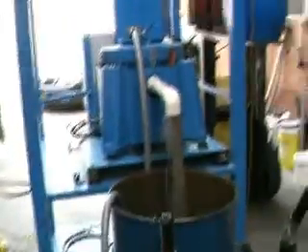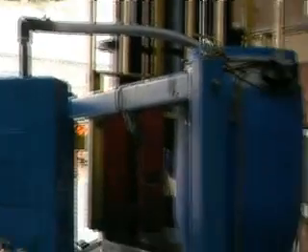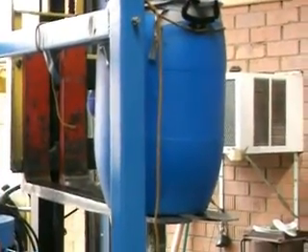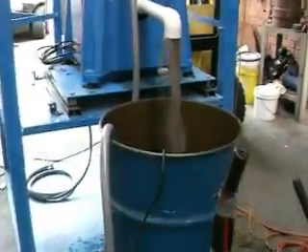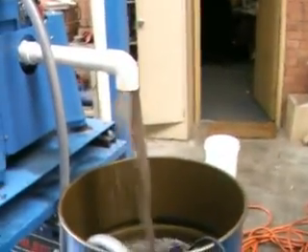Pulling about 2.8 amps, spinning at 3,000 RPM. I've got it set up so that the auto dump device dumps into this 100-litre barrel, and I've just got it on recirculation. The flow is about 60 litres per minute.